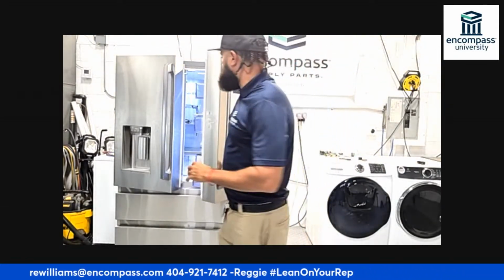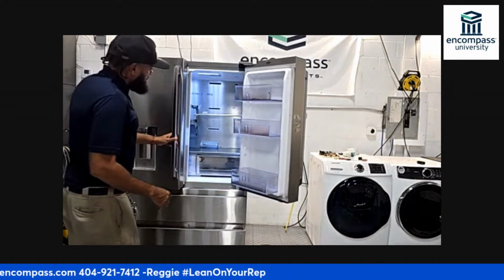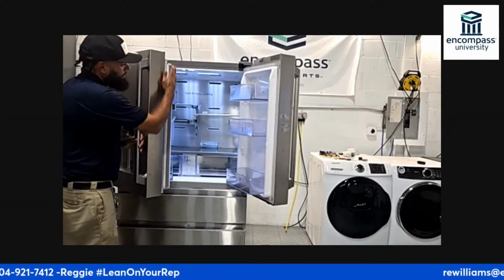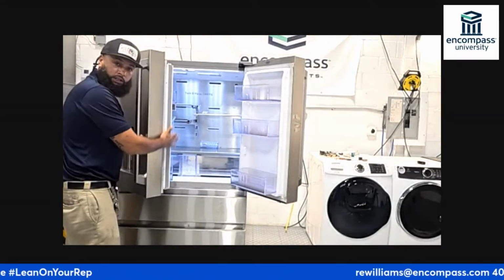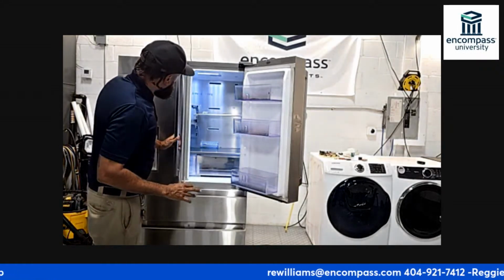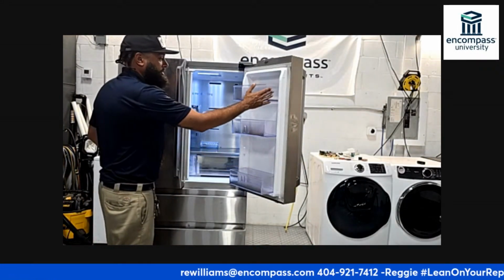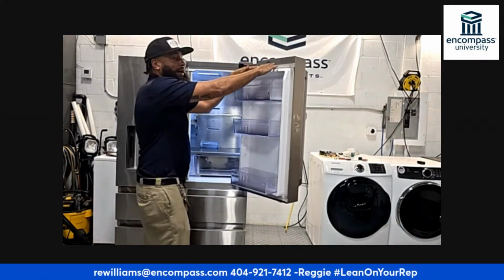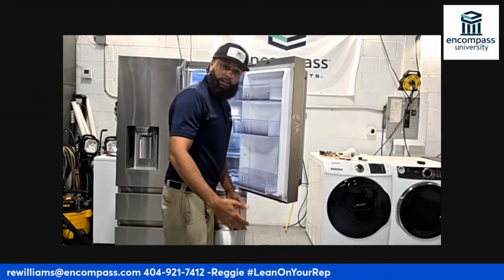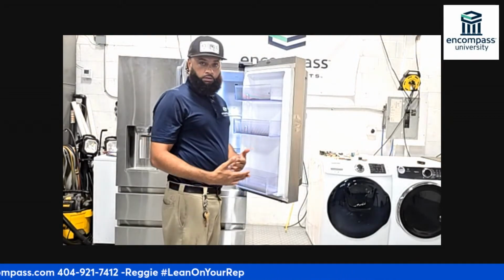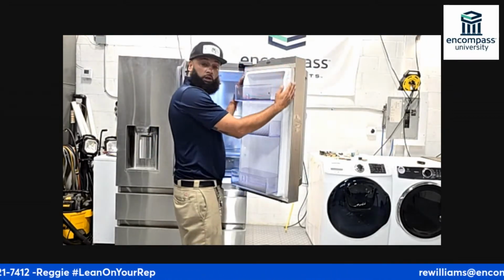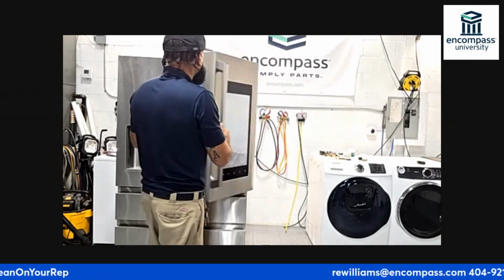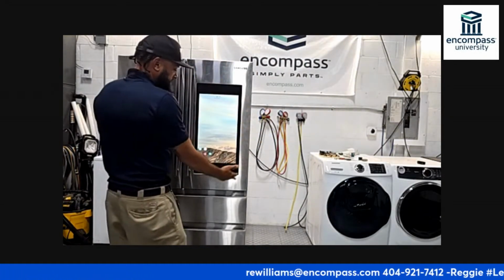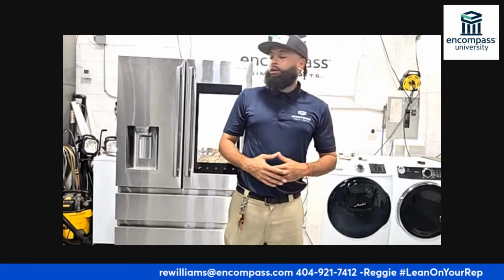There are other things I'm looking at too, like this flapper. I want to make sure this flapper is gently warm and that it's closing properly. I want to make sure my gaskets don't have any tears, rips, or creases, that they're all making a good seal, and that I've got good insulation around my top cavity.